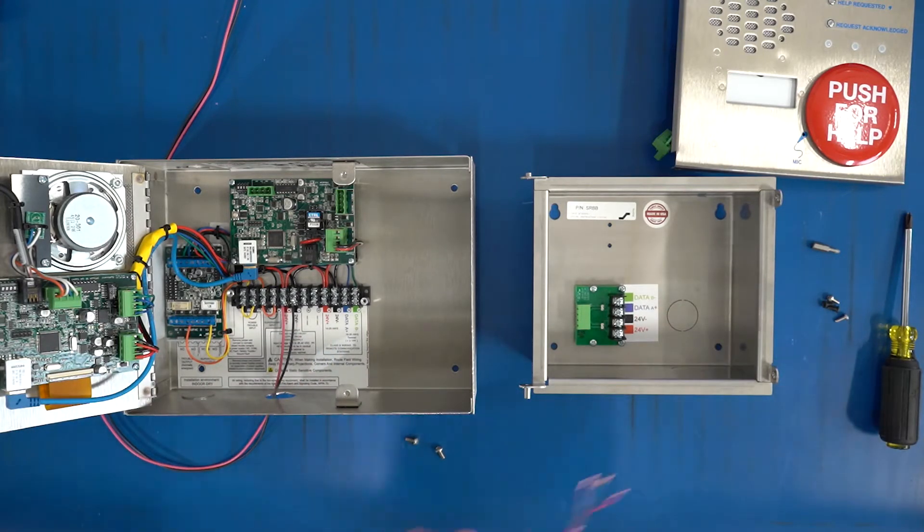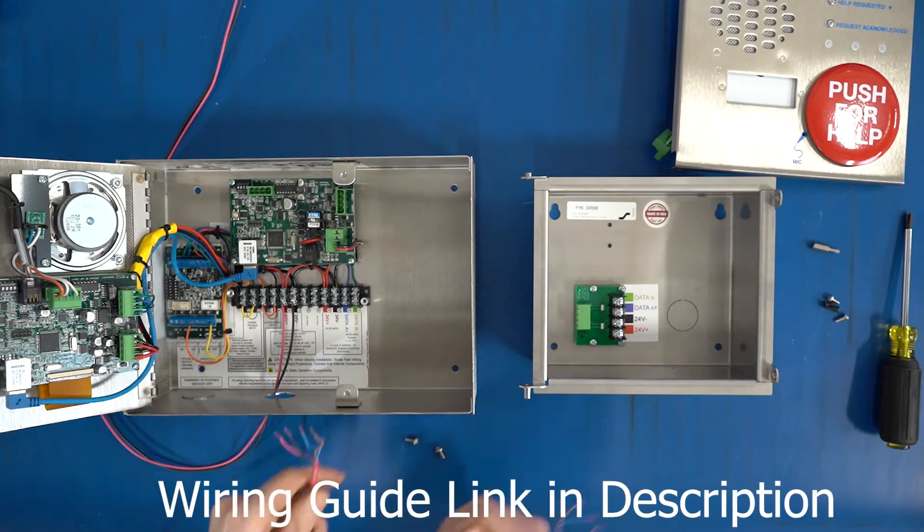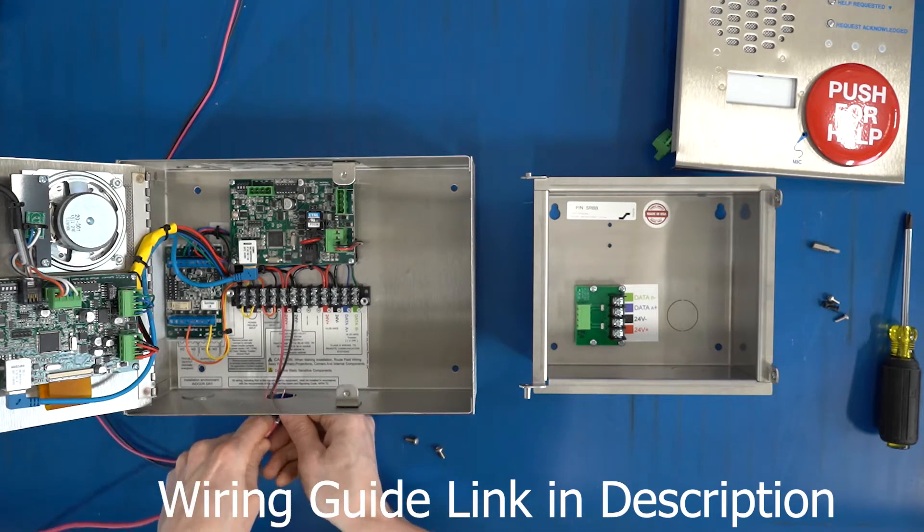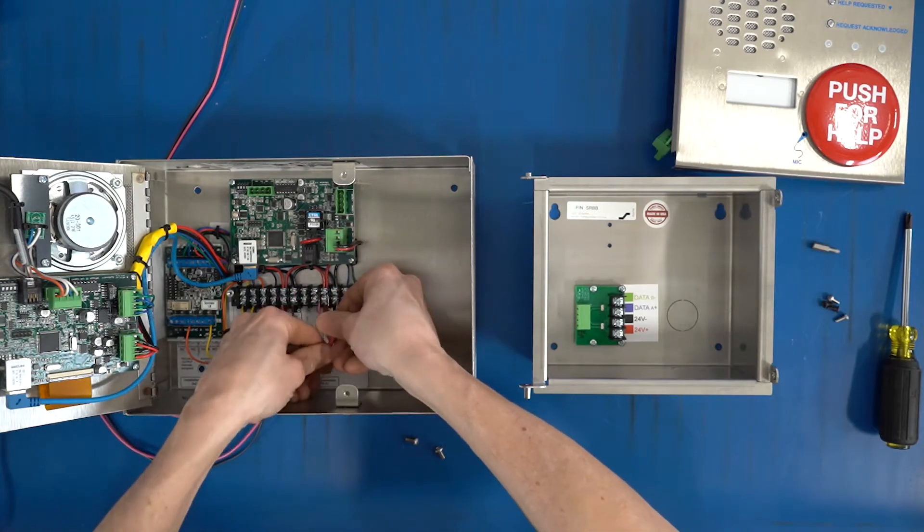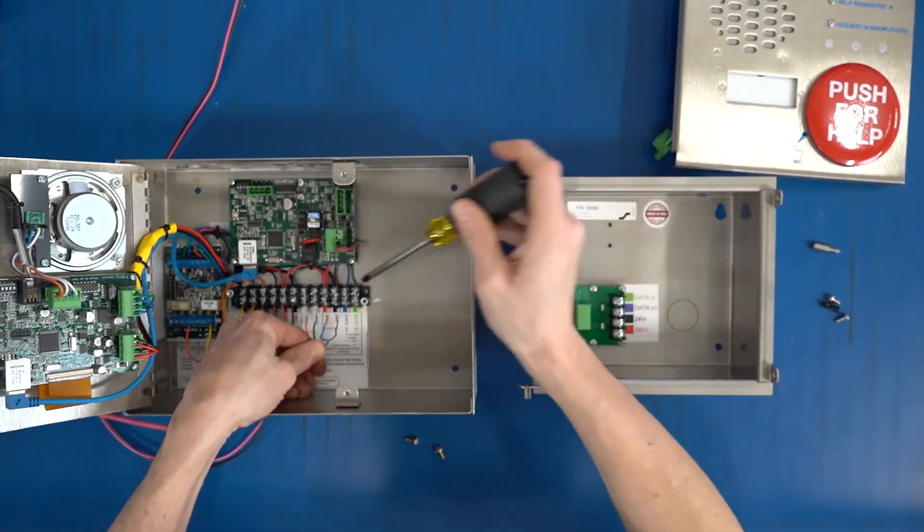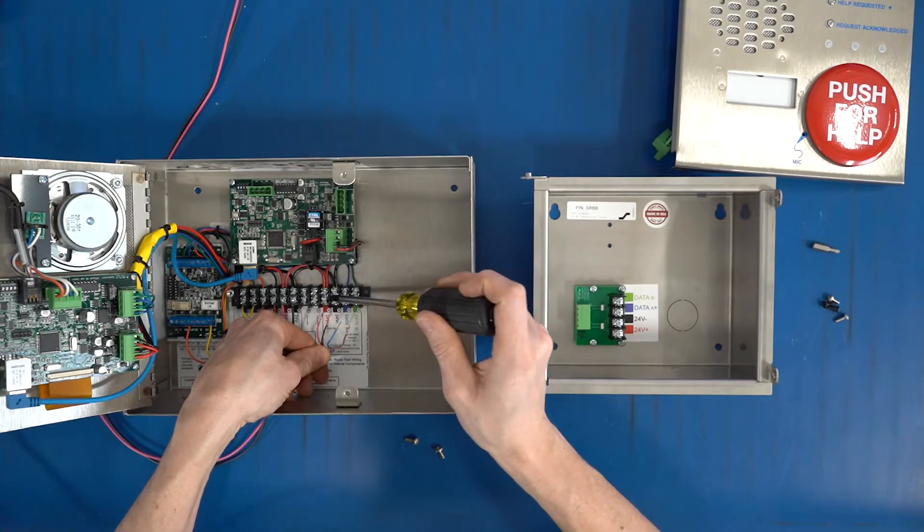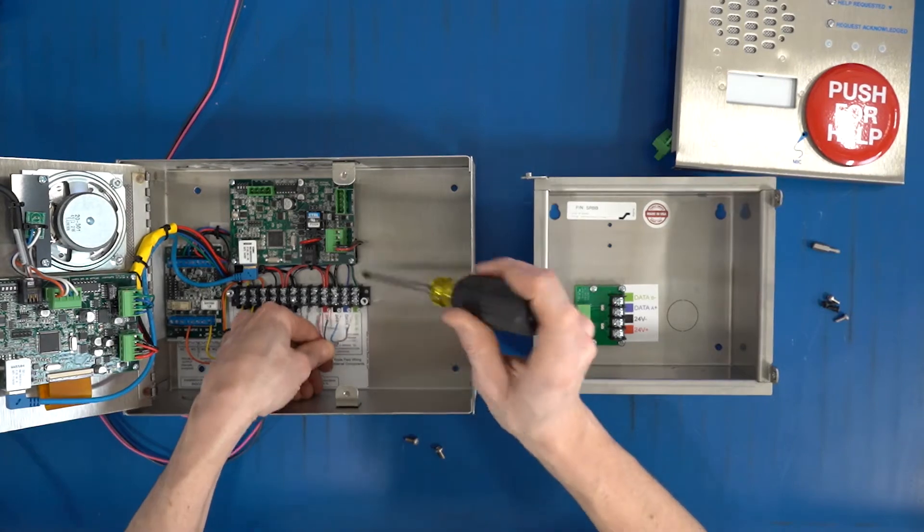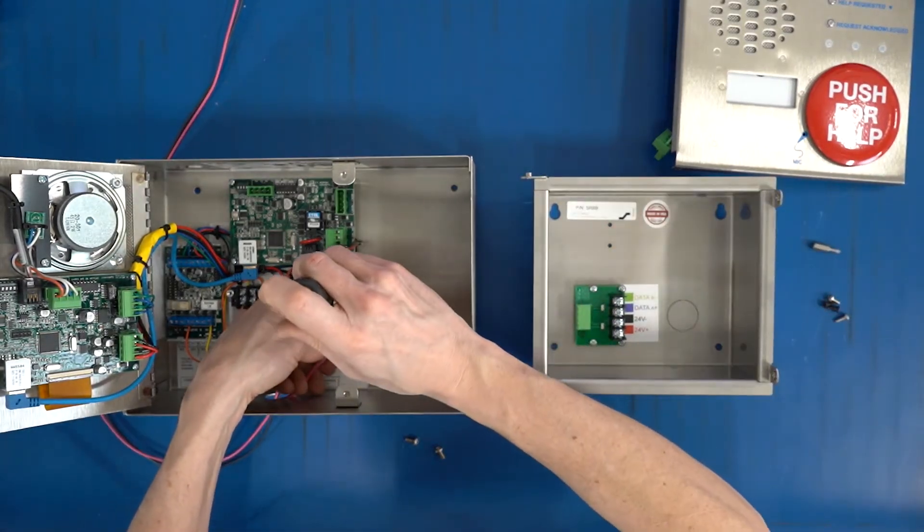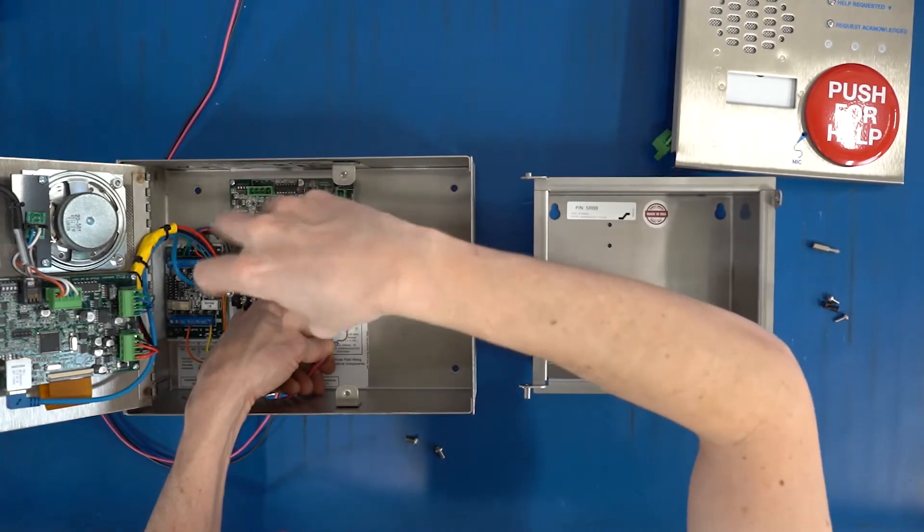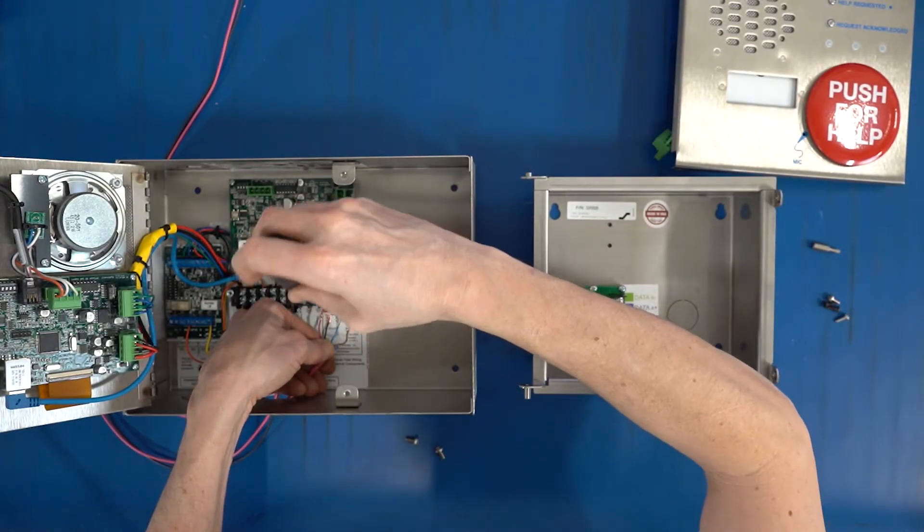I've got a piece of 18 gauge solid FPLP wire which we're going to use to wire this up. As you see, I've already got the wire bent as I've done this a couple times. So we're just going to attach this to the terminal strip. I'm going to use red to red, black to black, blue to blue, and in this case brown to green. I'm going to do the same thing on both, so we're just going to loosen all the screws here and attach the wires.